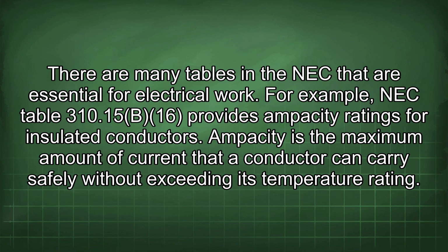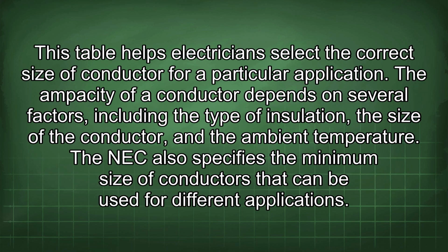There are many tables in the NEC that are essential for electrical work. For example, NEC Table 310.15(B)(16) provides ampacity ratings for insulated conductors. Ampacity is the maximum amount of current that a conductor can carry safely without exceeding its temperature rating. This table helps electricians select the correct size of conductor for a particular application. The ampacity of a conductor depends on several factors, including the type of insulation, the size of the conductor, and the ambient temperature. The NEC also specifies the minimum size of conductors that can be used for different applications.